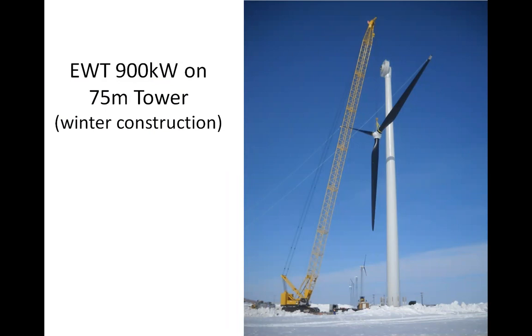This is a better shot of our large turbine, our EWT 900. These are on 75-meter towers, about the tallest tower you can get for it. In the background, between the crane and the tower, those are our AOC 50 kW Atlantic Orient Corporation turbines, installed in the late 90s, 1997, 1998 — much larger scale and much different technology. The smaller machines are induction generators with gearboxes. The larger machine is direct drive, variable pitch blades, all enclosed tower, much more friendly to work on in the elements.